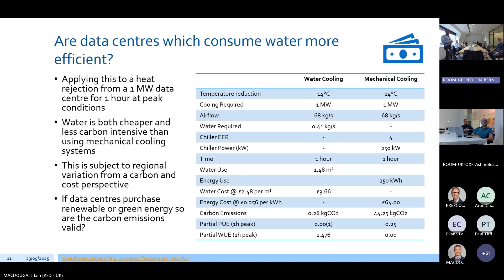So, therefore, looking at it slightly differently, if we look now at the peak power, we can look at how much power is actually used for that cooling, both from a water and a cooling perspective. So if we again take our evaporative system, we're cooling 1 megawatt of IT, we've got fan power losses, UPS losses, electrical loads and losses. We take them the same on both systems, and we have a cooling power because you still need some cooling even with the evaporative system. And you end up with a peak PUE of about 1.35 for the evaporative system, or 1.5 for the dry system. Again, these numbers are just simple assumptions to demonstrate the principles.